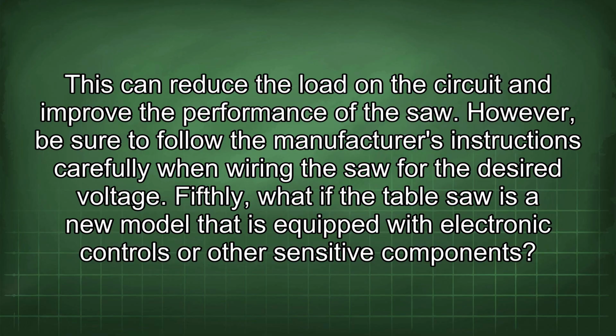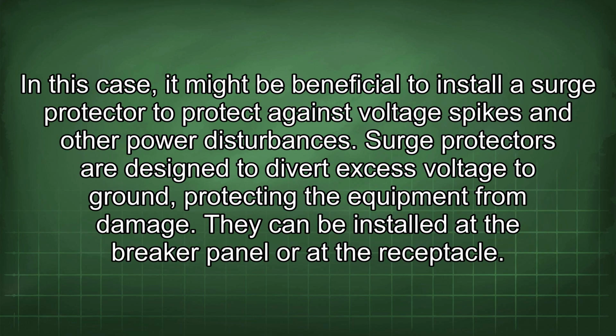Fifthly, what if the table saw is a new model that is equipped with electronic controls or other sensitive components? In this case, it might be beneficial to install a surge protector to protect against voltage spikes and other power disturbances. Surge protectors are designed to divert excess voltage to ground, protecting the equipment from damage. They can be installed at the breaker panel or at the receptacle.